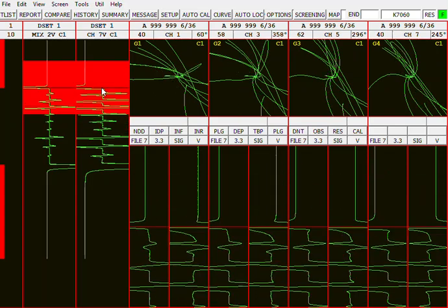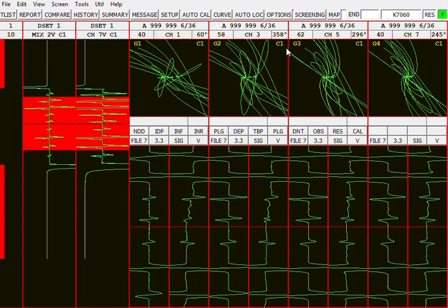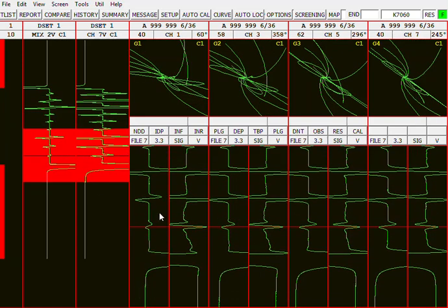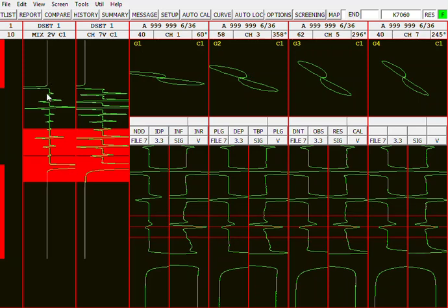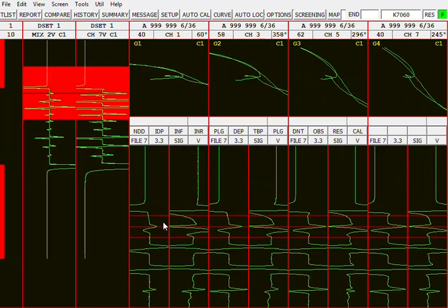Now, when you record heat exchanger tubing data, once you hit the record button on your data acquisition tester, the data starts to scroll in from the top of the strip chart, and the earliest in time data ends up at the bottom of the strip chart once you stop recording. The latest thing that the system recorded is up at the top of the strip chart. So when the bobbin probe was inserted into the tube and retracted while it was recording, this signal at the bottom here is the first indication that the probe saw, and this indication at the top of your long strip charts is the last thing that the probe saw.